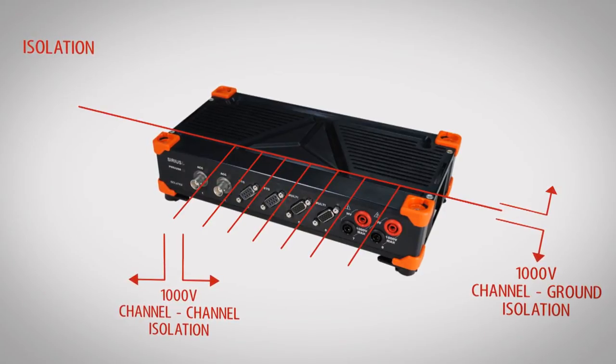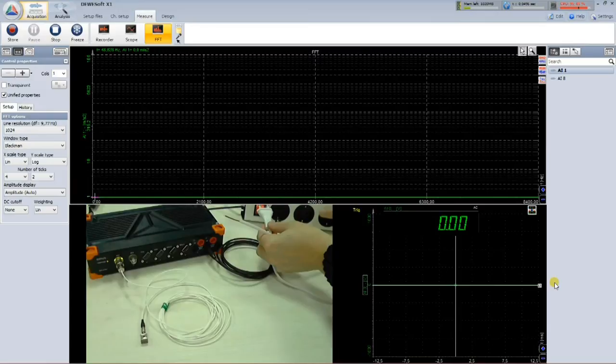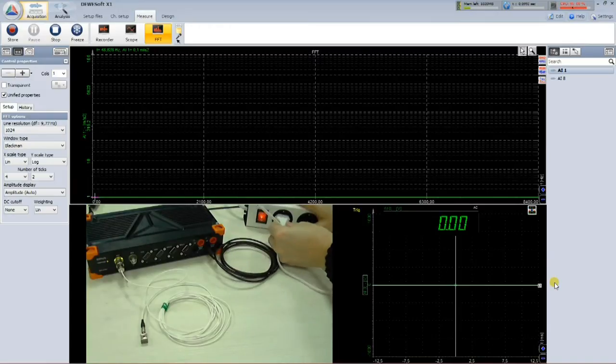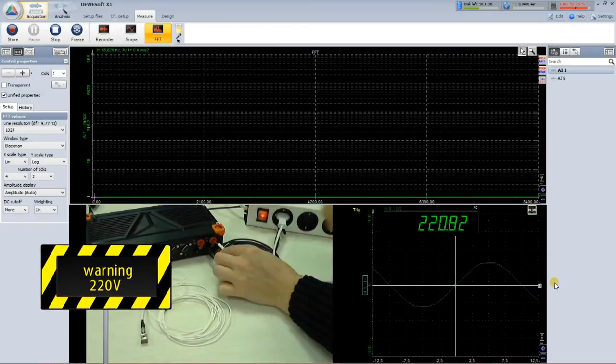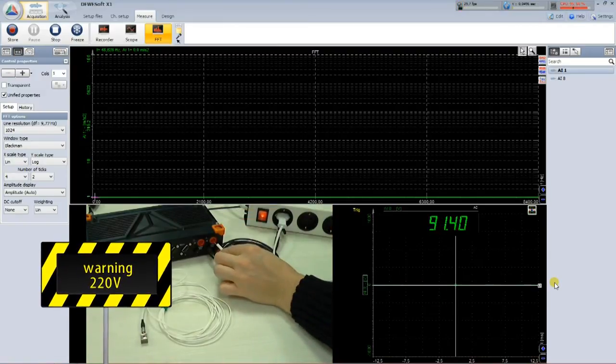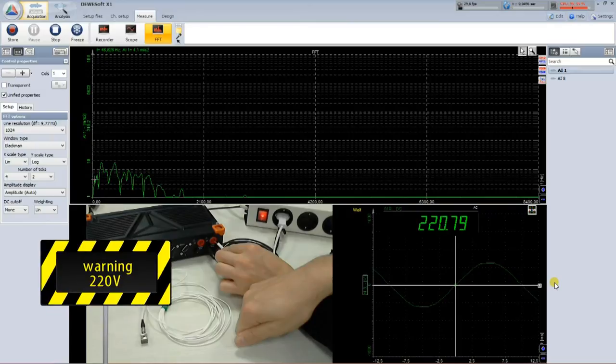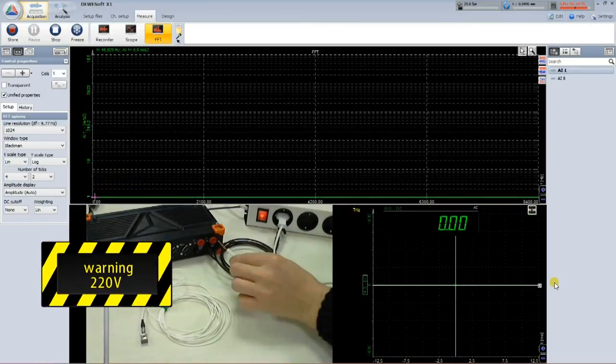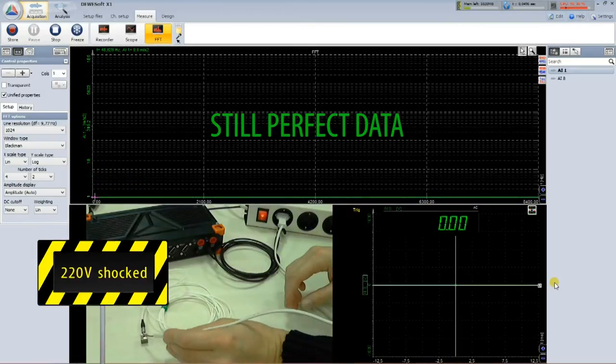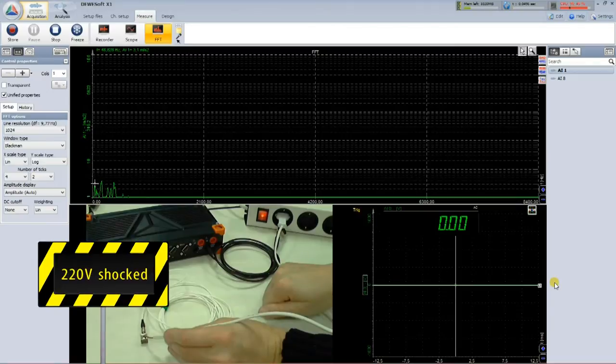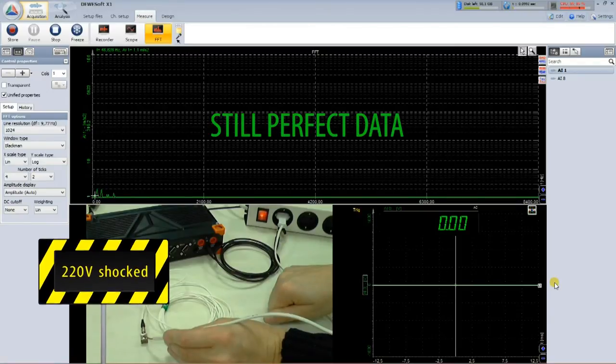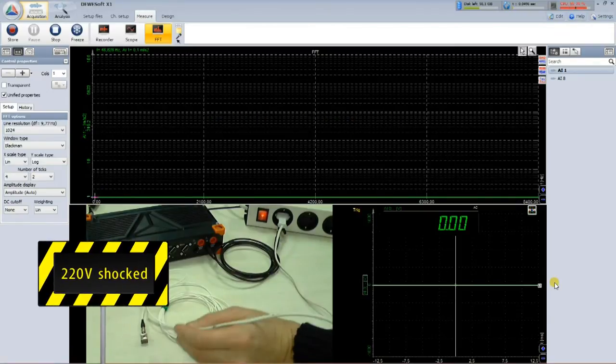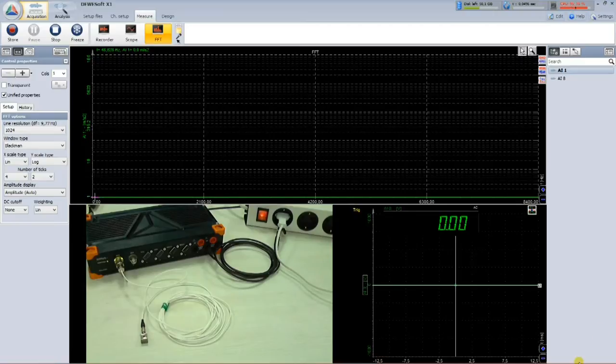But don't think only about high voltage measurements. Also, with vibrations, temperature, or any other measurement using non-isolated sensors, the sensor is often placed on a part of the machine with high voltage potential against the measurement system ground. Non-isolated measurement devices would burn in such case or at least give wrong results. With SIRIUS, it is now just one less thing to worry about.